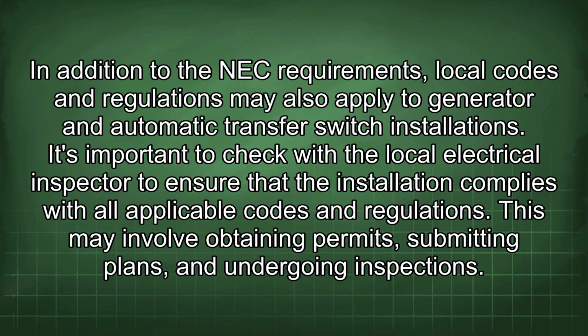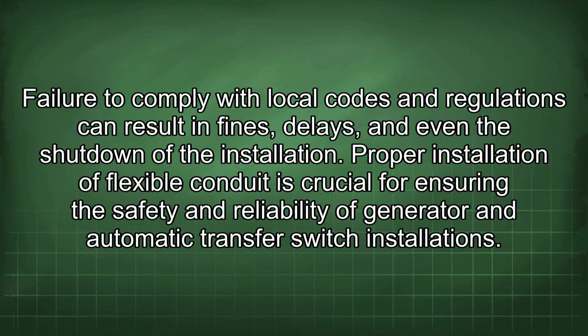In addition to the NEC requirements, local codes and regulations may also apply to generator and automatic transfer switch installations. It's important to check with the local electrical inspector to ensure that the installation complies with all applicable codes and regulations. This may involve obtaining permits, submitting plans, and undergoing inspections. Failure to comply with local codes and regulations can result in fines, delays, and even the shutdown of the installation.